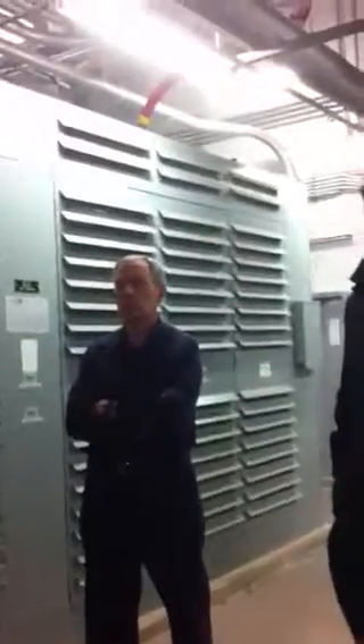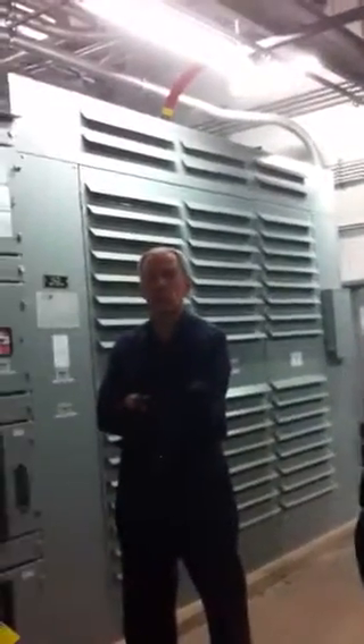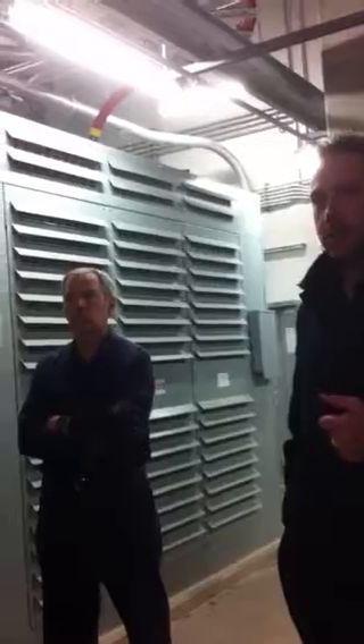So a lot of people, when we're going through design phase, say, why do you have two transformers in here that are the exact same size when one can run the building? Why do you have that redundancy? The downtime at the university is far more costly than the cost of an extra transformer and an extra main tie main board. If you lose a transformer in this building, you do not just go out and buy a new one and have it here over the weekend and the building is up and running again.